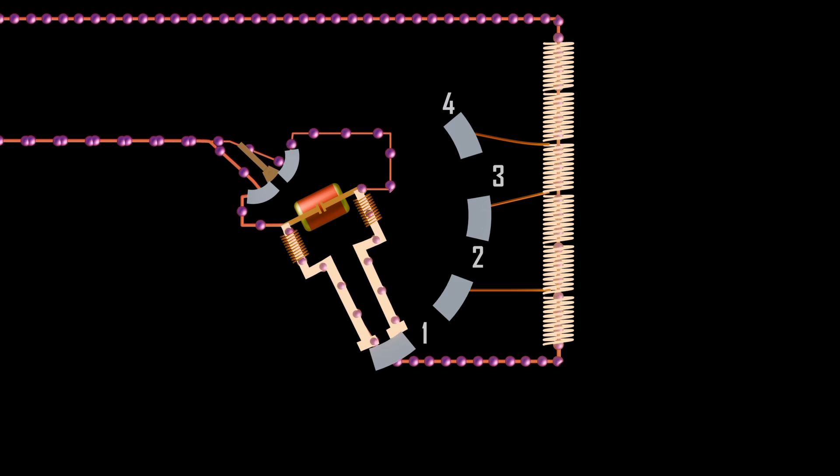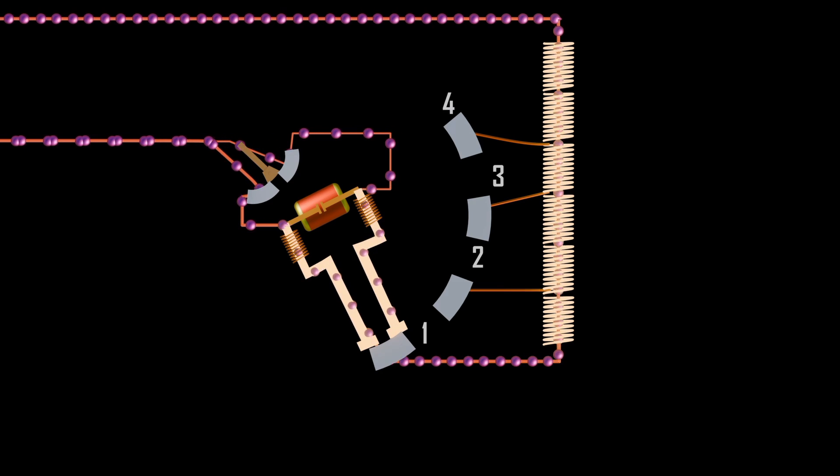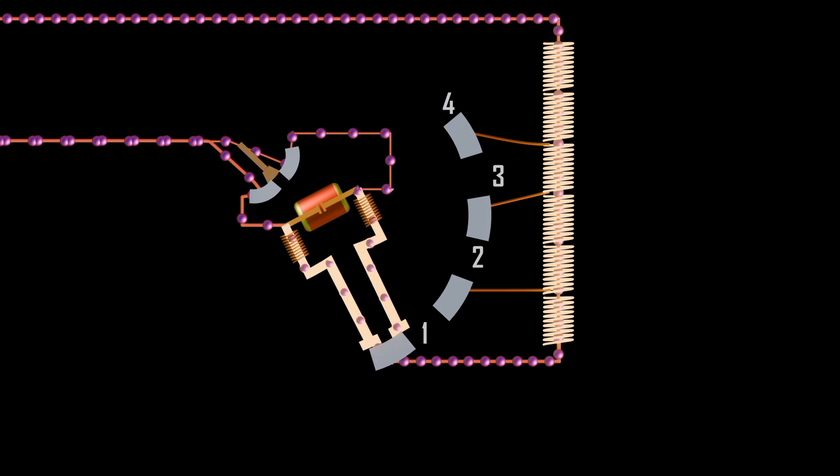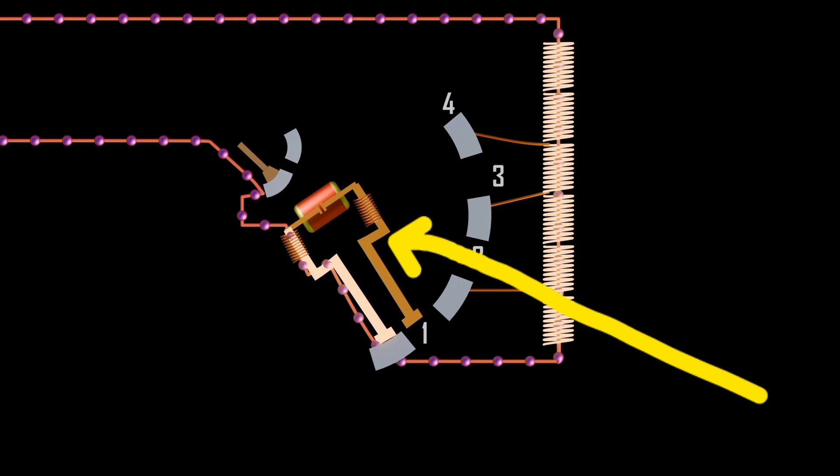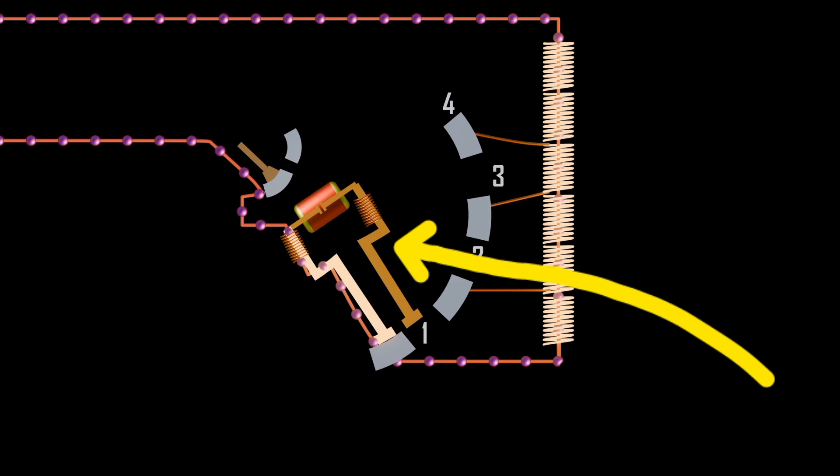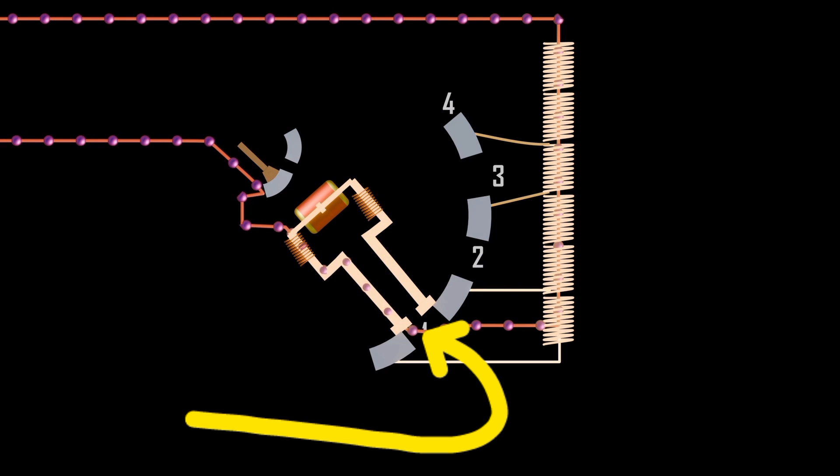When we want to move from tap one to tap two, the bypass switch switches to the first contact, meaning no current to the other contact. At the same time, we can move the selector switch, hence one side of the switch is not energized. Then with one side of the bypass switch not energized, we can still move the selector switch. Then both contacts of the selector switch are in contact with tap one and tap two.